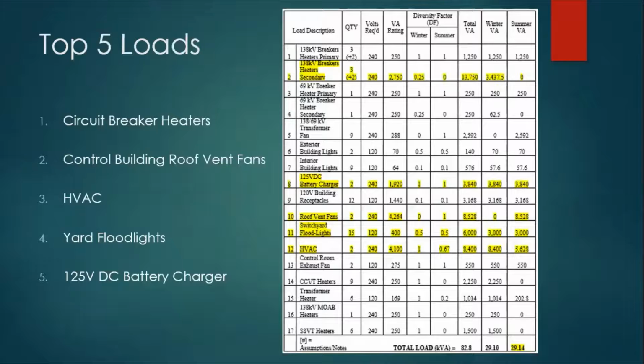The top 5 loads that affected the total substation demand included circuit breaker heaters, roof vent fans, HVAC, yard floodlights, and the 125-volt DC battery charger that was selected in conjunction with the DC battery study to charge at the recommended rate. These loads ranged from 13.7 to 3.8 kVA, respectively. Each load was given an assumption or link to actual equipment as a quality control check to verify realistic values.